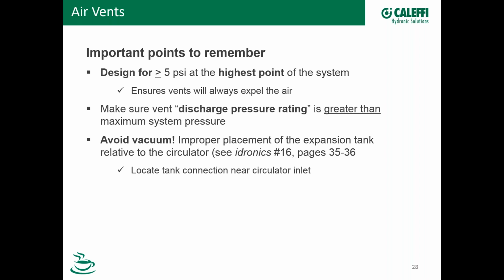Again, avoid a vacuum. We've been talking about this, but if you put the expansion tank in the wrong location relative to the circulator, you can draw a vacuum. Now, if anybody wants to see how this works, look at idronics pages 35 and 36. There's a really good explanation there in our idronics journal on what that looks like. So you want to make sure and locate the tank near the circulator inlet. Install the vent as vertical as possible. Again, like the reasons we talked about, if it's off a little bit, that float might ride up and down on the inside wall of the vent, and over time that can stick or maybe not work as well as it should.